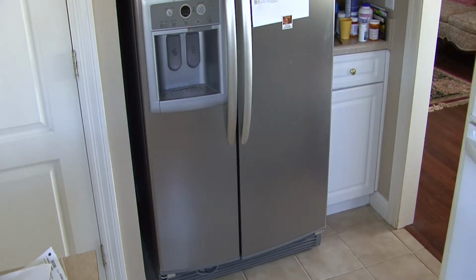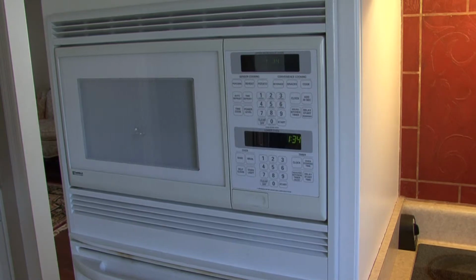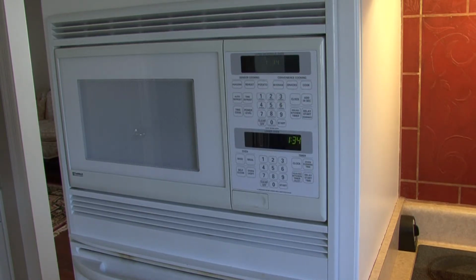So what is required when plans are submitted on the electrical side of it is that voltage calculations need to be conducted on each circuit that is in the housing diagram to assure that, such as in a kitchen circuitry, if you were to plug a refrigerator in that receptacle, then there would be an adequate amount of voltage to run that refrigerator. As in with any other circuit that's in there, whether it's running a toaster or a microwave or other things.